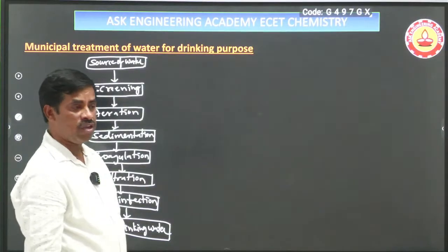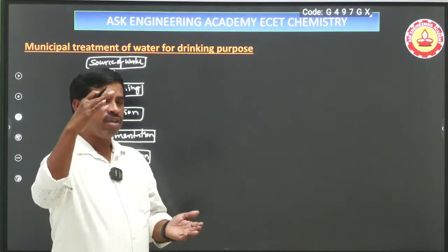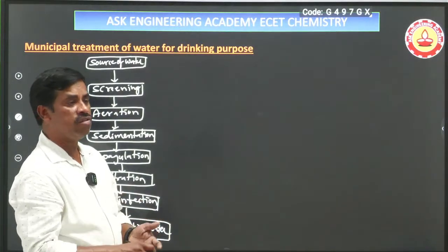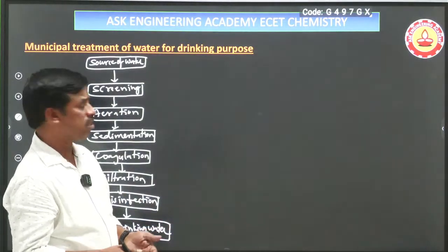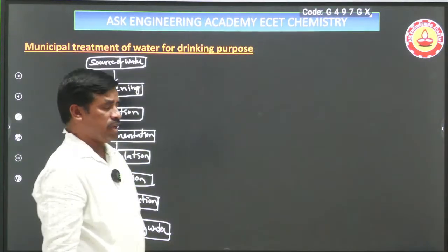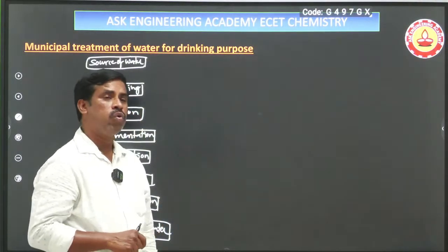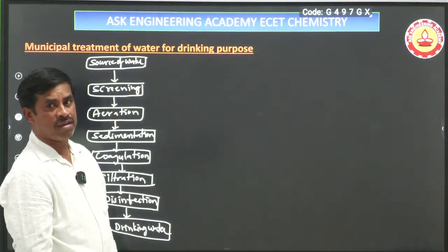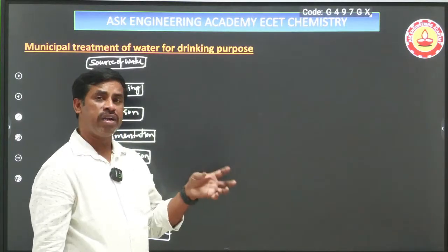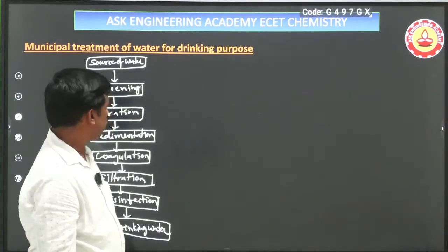Why it is called aeration: whenever the water is kept in an open vessel in the environment, the oxygen concentration in the water increases, and then it removes dissolved manganese, nickel, copper, zinc, etc. That is the aeration process. Sedimentation process: in sedimentation, dissolved suspended impurities must settle to the bottom of the tank due to gravitational force. It cannot remove 100% of the impurities, only about 75%.